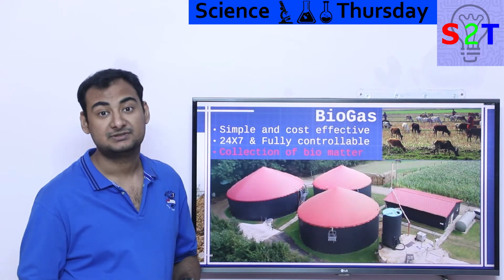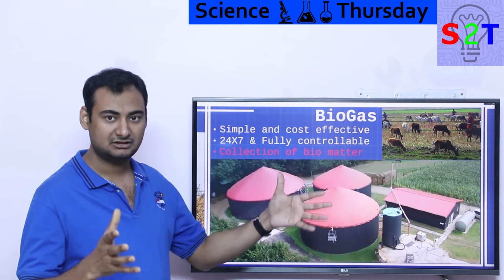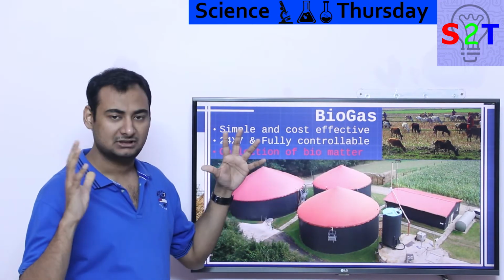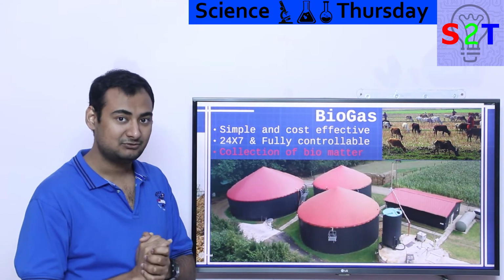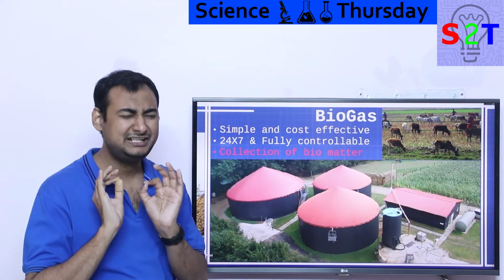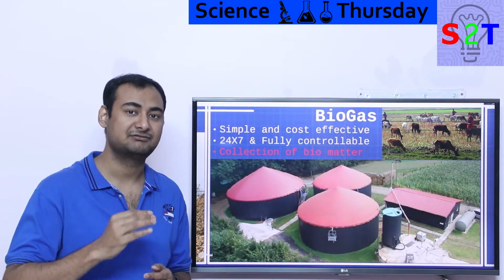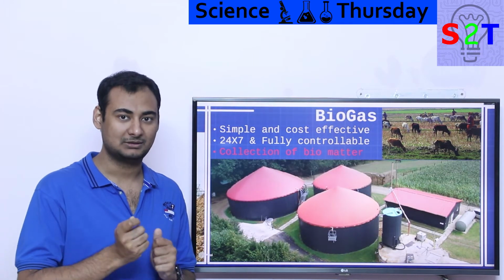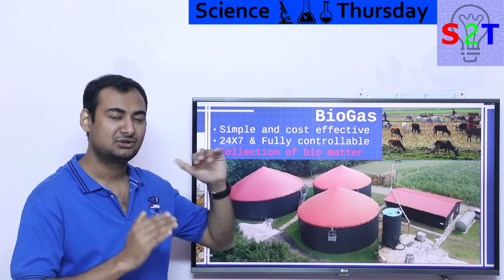Now that is a very unique aspect of biogas, because it's a chemical system. Let's say you take a town, or small villages, and you say I'm going to build a biogas power plant. Then you can also add a solar farm there. You will have a grid-tie system where your biogas plant works on minimal capacity. Generally, big generators in the megawatts do not like to spool up or spool down too quickly, so you keep them running at bare minimum and keep adding solar.